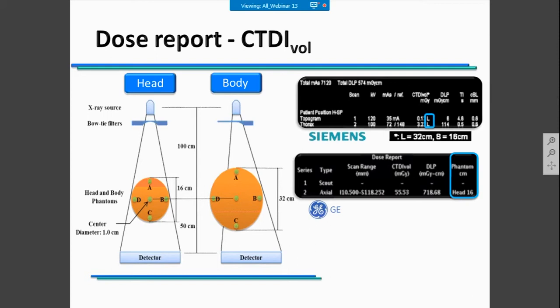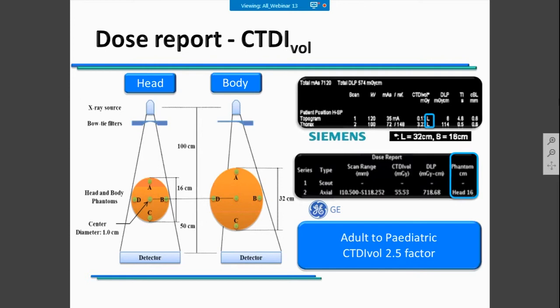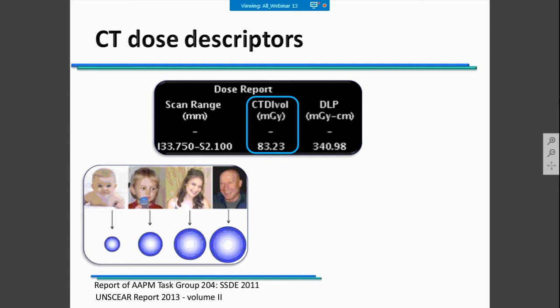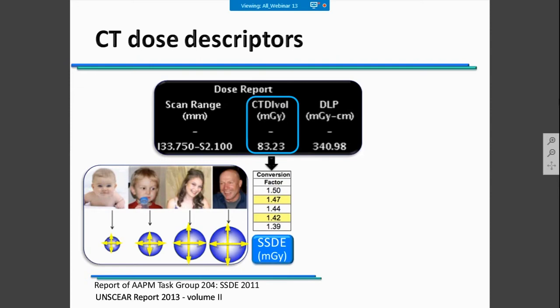If you are using a General Electric CT scanner, you should also analyze the information about the phantom that was used to calculate CTDI vol. It's also important to state that if you are looking at pediatric CT examinations, CTDI vol calculations must have a factor of 2.5 included. CTDI vol also has a lot of limitations. It represents a value for different patient sizes, and it's important to analyze, especially for body regions, the impact of patient size on these values. For this, you could use specific size-specific dose estimates based on converting CTDI vol values using a conversion factor to calculate SSDE.